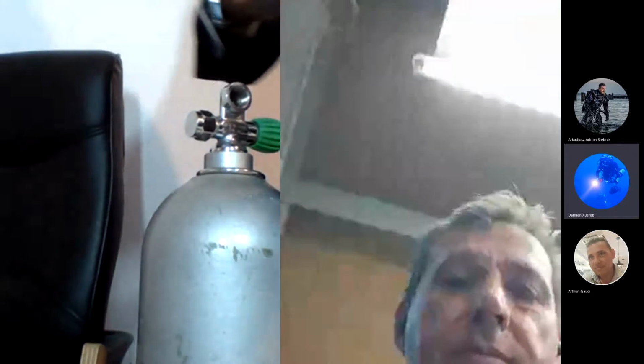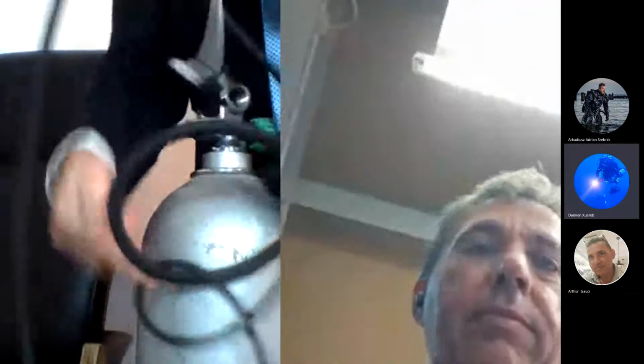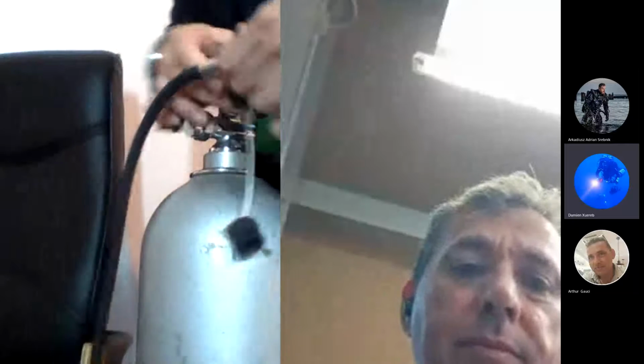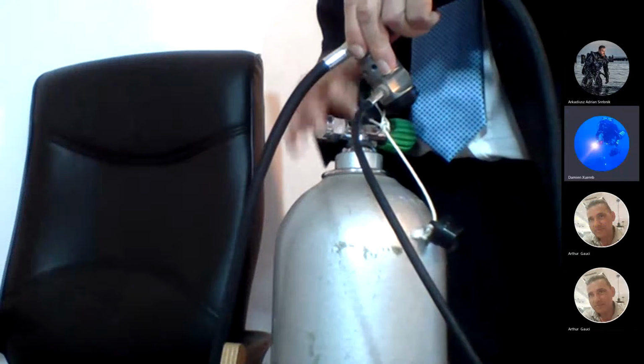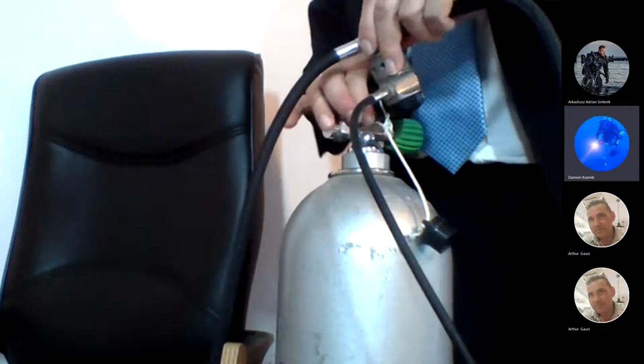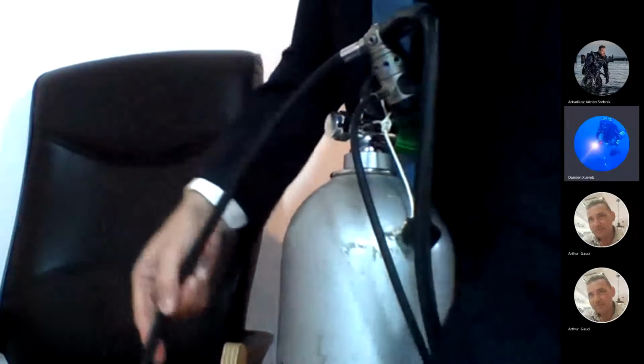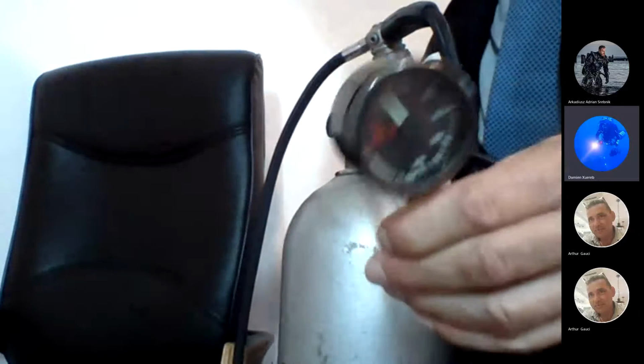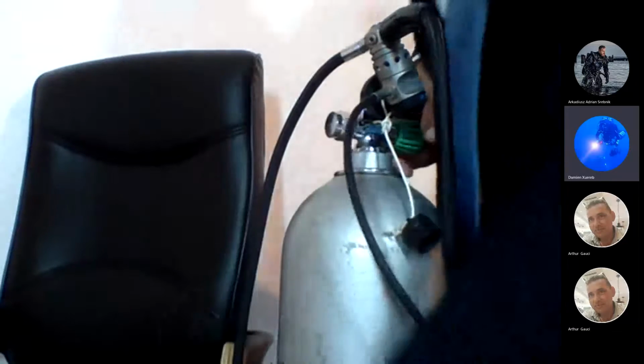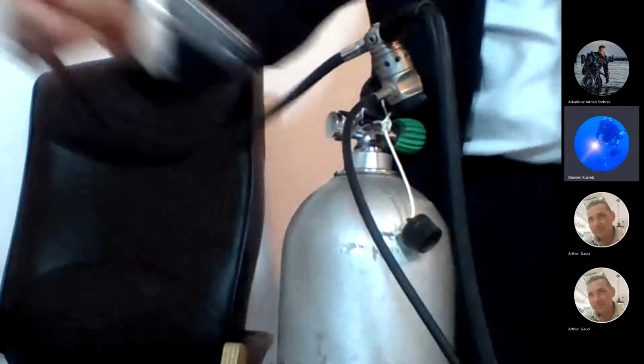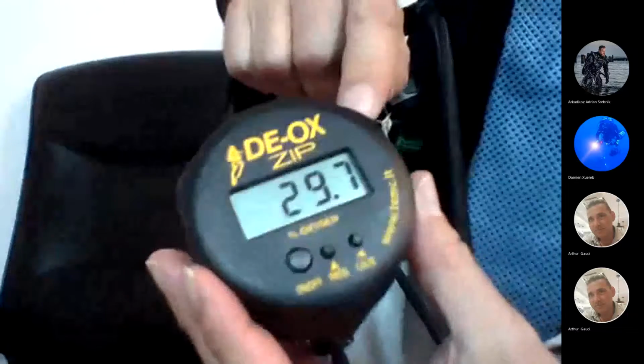Okay, now I go with a regulator. Well, this is a standard cylinder, 110 bar, as I was having before with the other analyzer. Then I can use the hole here. Look, the sensor is 29%. It doesn't go down. I don't care, I already did the calibration.